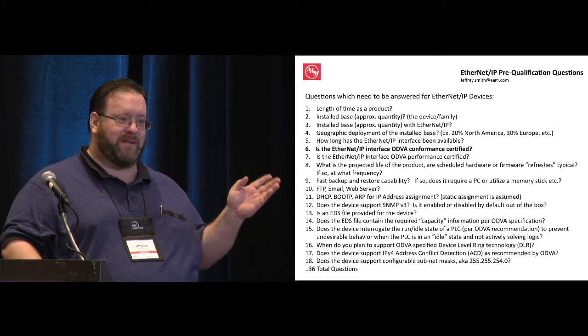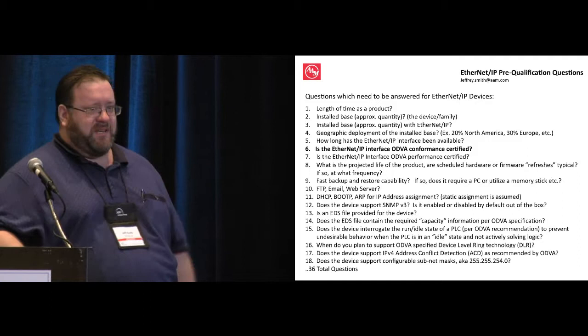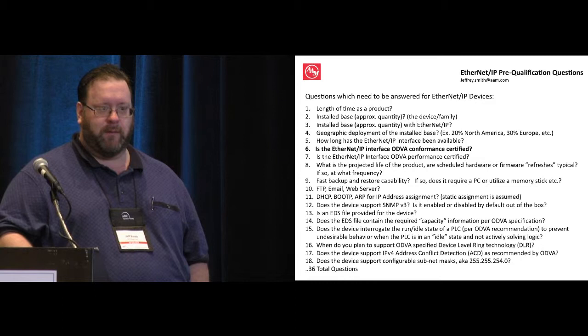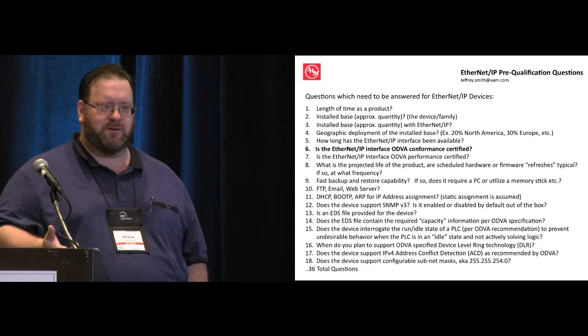When we select a device, we test it pretty heavily. So there's a couple of things that go along with that. If you look, it's some basic information. Number six is key. For us, the device must be ODVA conformance certified. We've also started moving towards pushing our suppliers to provide us performance certified devices. That's not something that they do a lot of today.